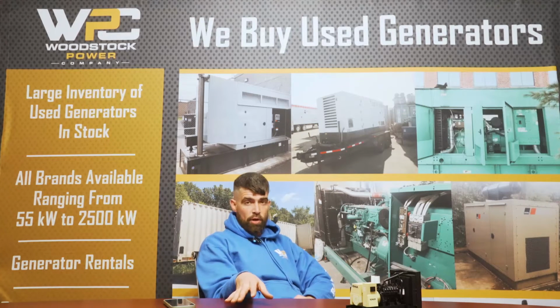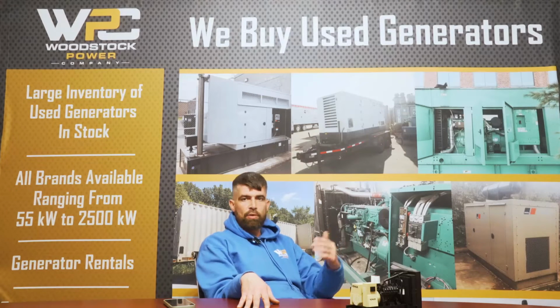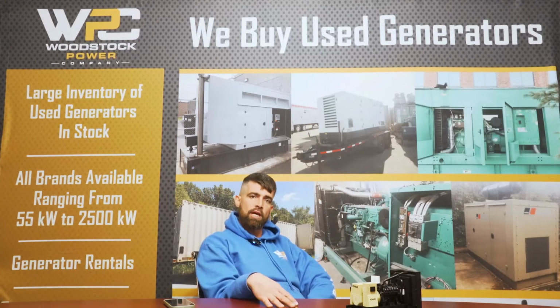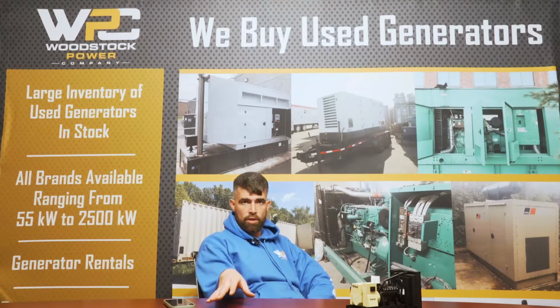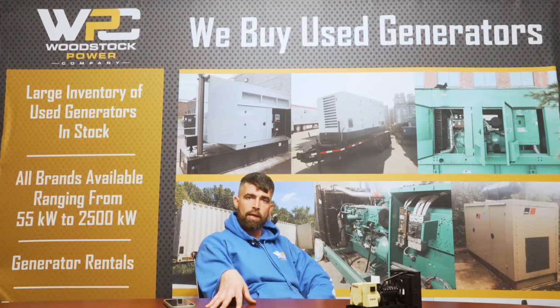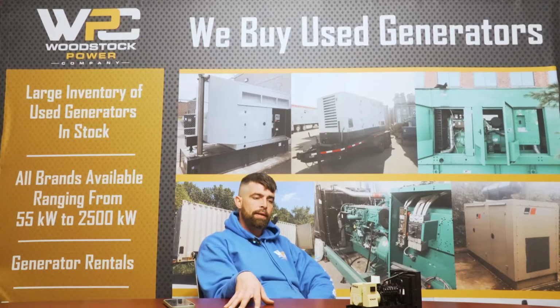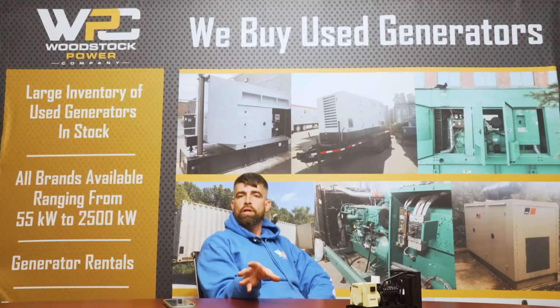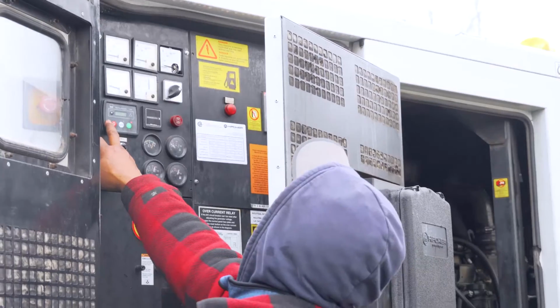Always recommend, especially in the wintertime, again, it depends where you live and the temperatures in the area, to have an extra set of batteries on hand, just in case your other ones go dead. You can always replace them and have your power back and won't have to rely on charging them again. And from there on out, the next issue will be what we call your common alarms.